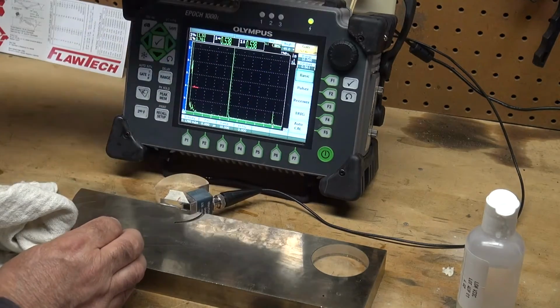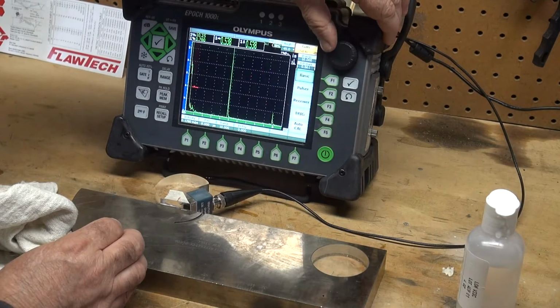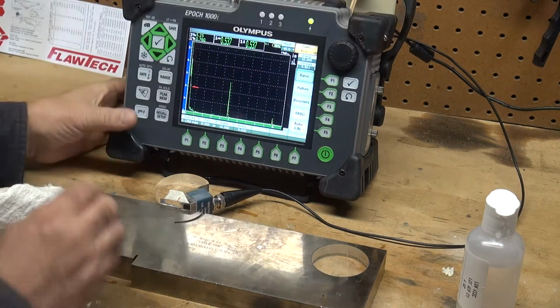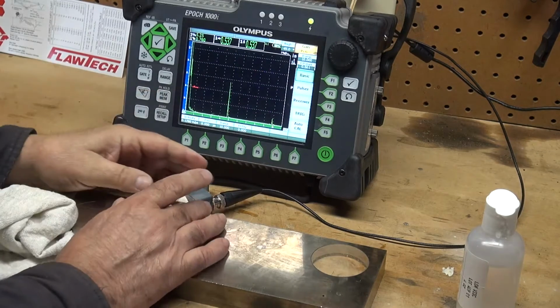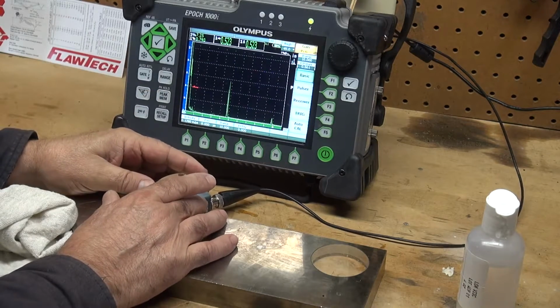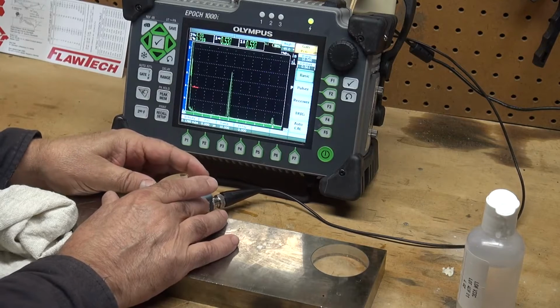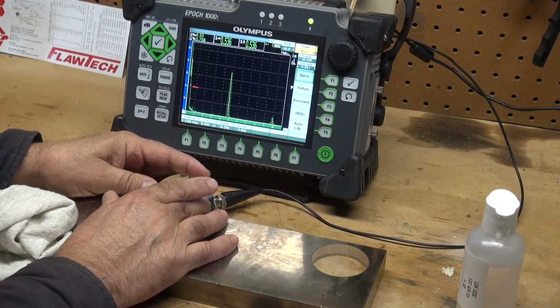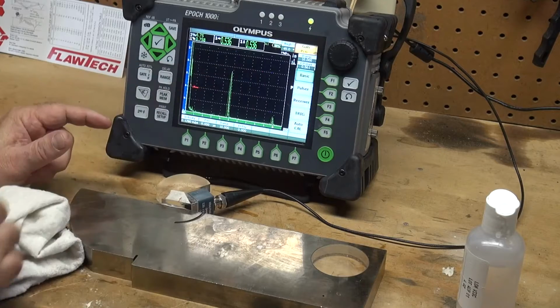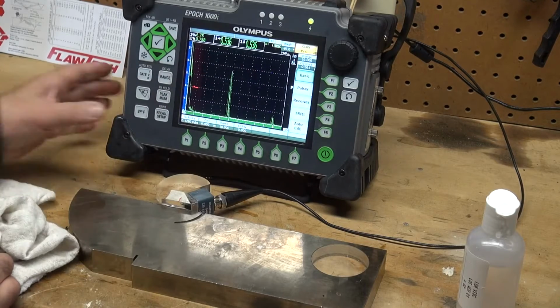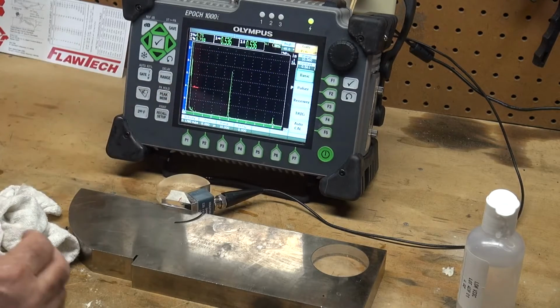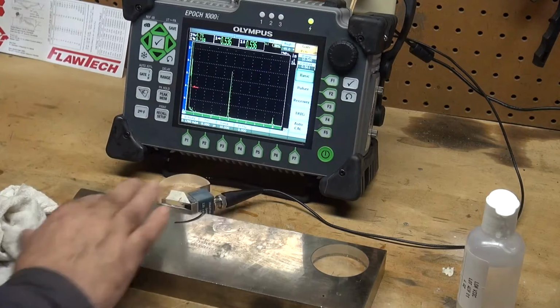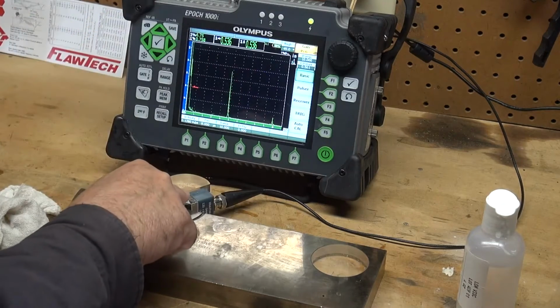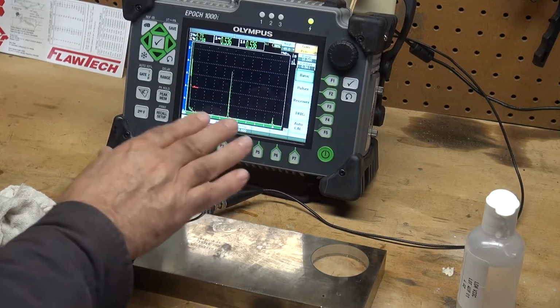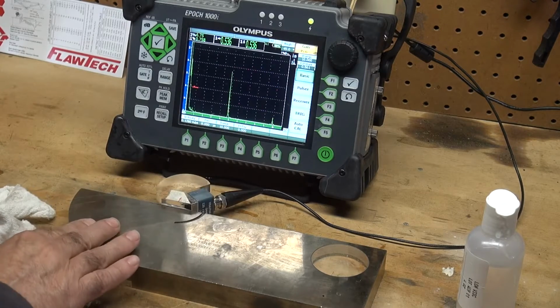What I want to do is find my beam index point. So I'm going to take out some energy here. Reduce my dB. I'm going to hit my peak memory, and I'm going to move my transducer back and forth. And we will see right there, I'm in the middle of the curve of my traced peak memory. That is the maximum energy I'm getting back. That's the sweet spot where this wedge works with this block.